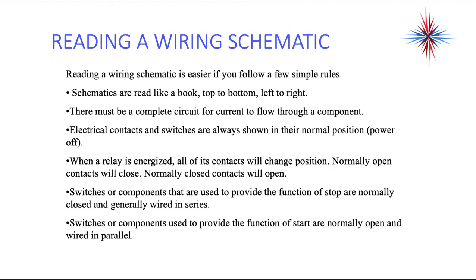When a relay is energized, all of its contacts will change position. Every normally open contact will close. All normally closed contacts will open. Switches or components that are used to provide function of stop are normally closed, and they're wired in series. Switches or components that are used to provide a function of start are normally open and wired in parallel.